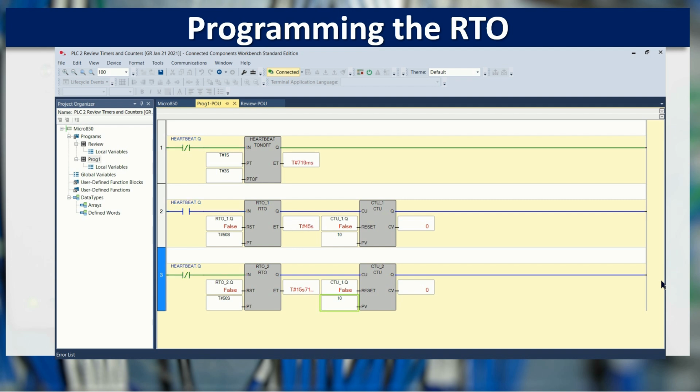It could be that the pump was supposed to be turned on, it didn't turn on. We take the contactor that says, oh, I'm supposed to be turned on by the logic, but for whatever reason, maybe the overloads are gone, my contacts didn't close, I didn't see that.